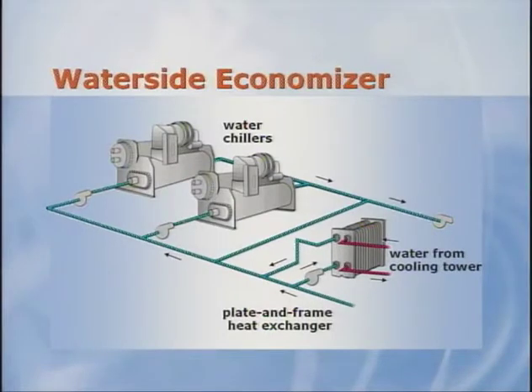Now earlier for the self-contained VAV system, I described a water-side economizer coil that was used to pre-cool the air. Another configuration of a water-side economizer is to use a plate and frame heat exchanger to pre-cool the water that is returning to the chiller plant. In this configuration, the heat exchanger is also connected to the condenser water system. When conditions allow and the cooling tower is able to make cold enough water, this cool condenser water is used to pre-cool the water returning from the air handlers, reducing the cooling demand of the chillers and saving energy. This type of economizing strategy was used in the fan coil system also, where the dedicated outdoor air system was sized to provide only minimum ventilation. In that case, airside economizing is probably not feasible.